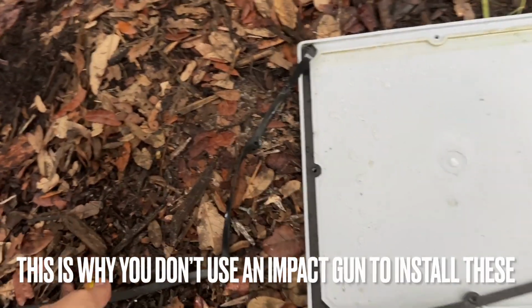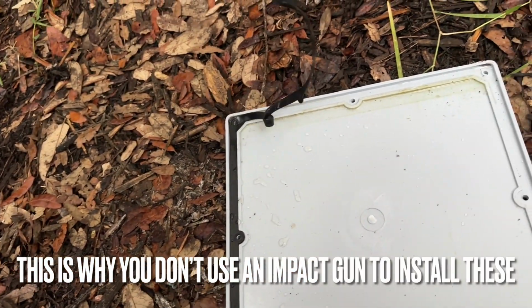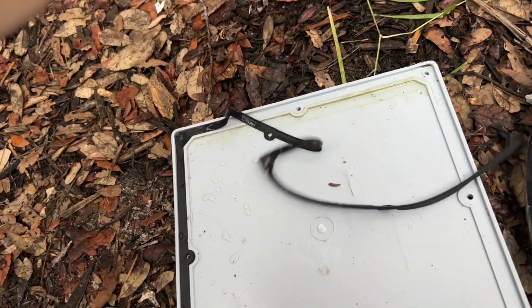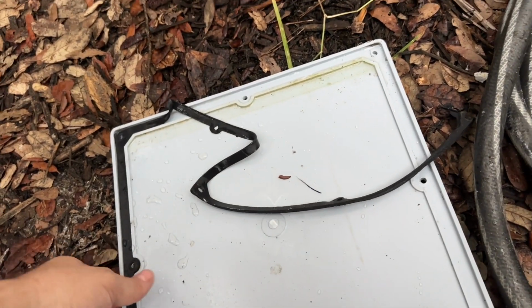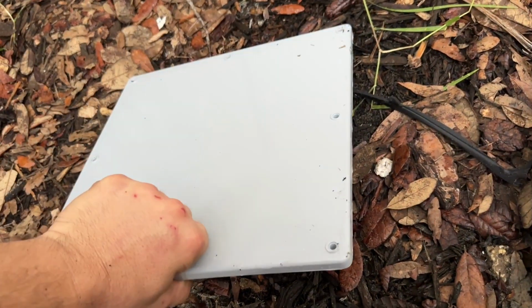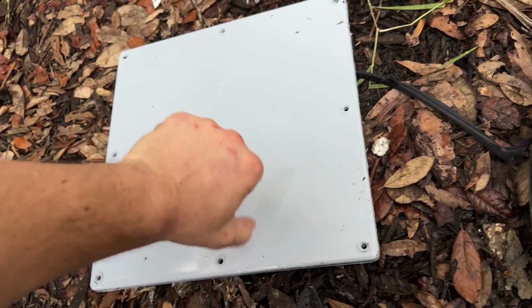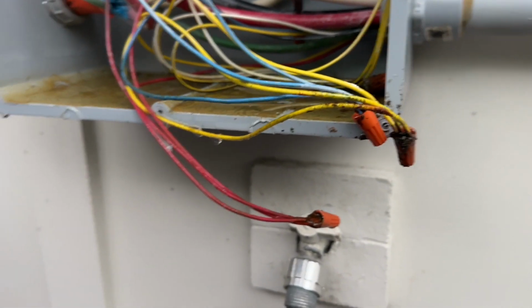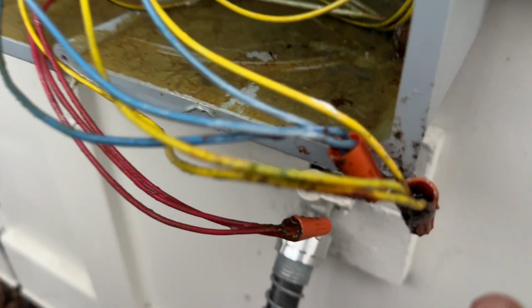Licensed electrician, this is how I pulled the box off. We had a split gasket on this exterior mount box, which was the failure point, which allowed the water to come in, because they also didn't have one of the screws installed. So here is all my problem, I believe. That error code indicates a voltage leak, and that will absolutely leak voltage.